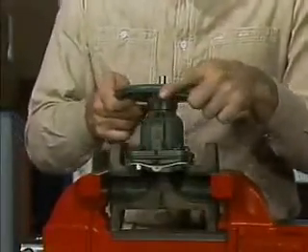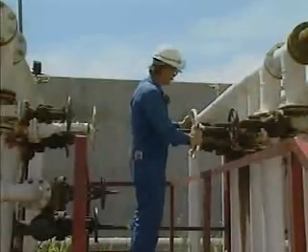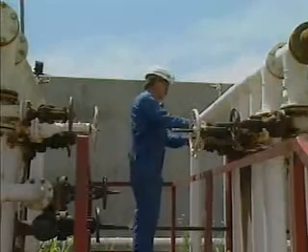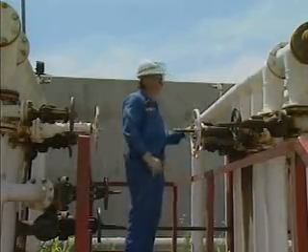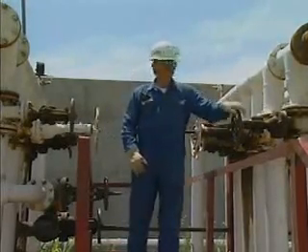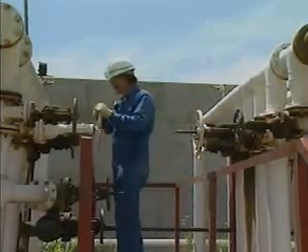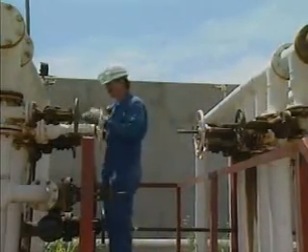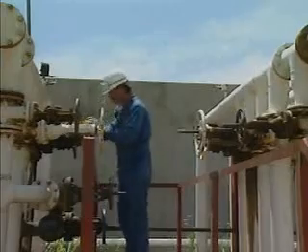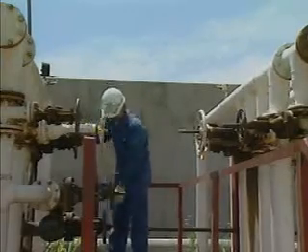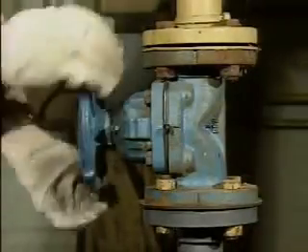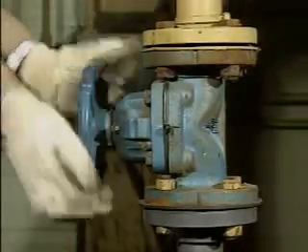When a hand wheel is used to operate a diaphragm valve, excessive force could cause the diaphragm to jam into the seat and be cut, resulting in leakage. Finally, to check if a manually operated valve is closed, try turning the hand wheel or handle in the proper direction to close the valve. This prevents undesired flow through the valve if it's not already tightly closed. Many valves can be operated manually with hand wheels or with operating handles.